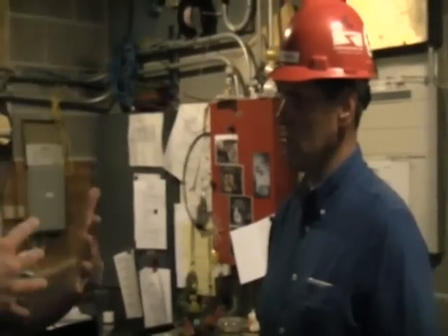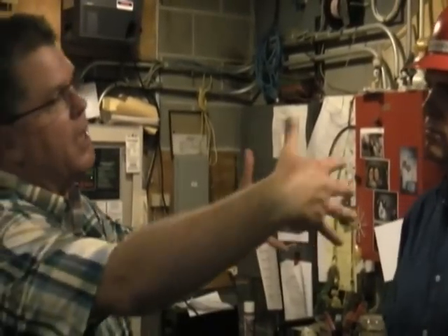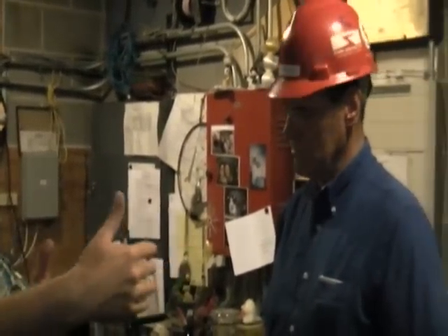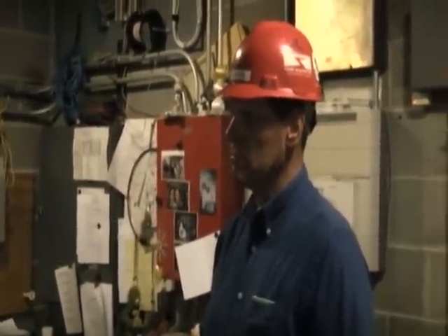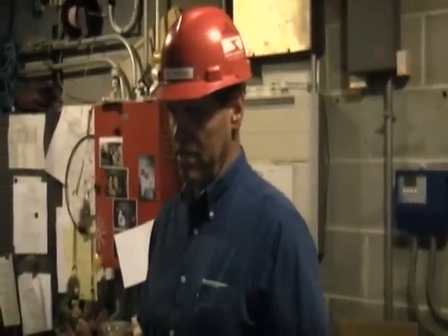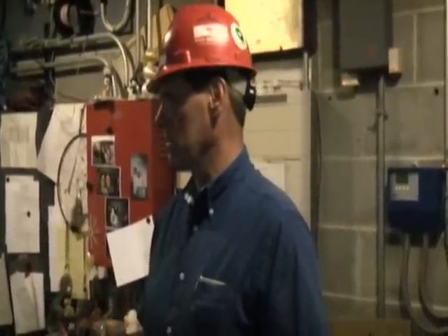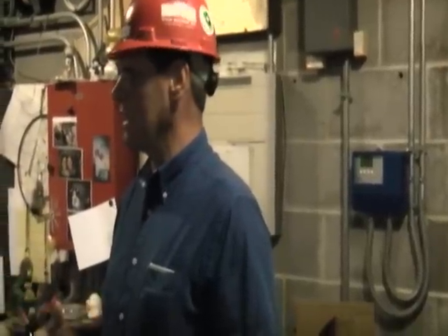For a panel that's in the open in a construction environment, can you talk about how you would set up the restricted area? With temp covers you still have to maintain your restricted area — it's got to be outside the arc flash protection boundary, you have to understand what the other trades are doing, and it's got to be big enough to be safe. Most definitely. NFPA 70E and OSHA both specify a flash protection boundary for energized work, meaning outside that boundary, if an arc flash explosion occurred, the most a person would be subjected to is a first degree burn. Inside that boundary, a person could receive a second or third degree burn — a serious, possibly life-threatening injury. The arc flash boundary is typically four feet, depending on the voltage, and we're typically dealing with low or medium voltage — 50 volts to ground up to less than 600 volts.